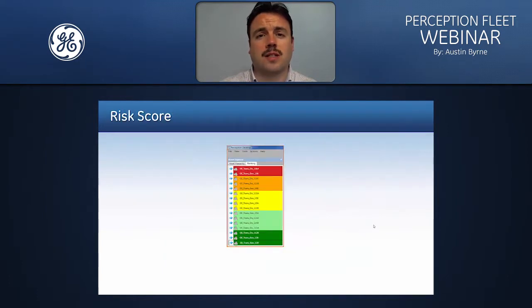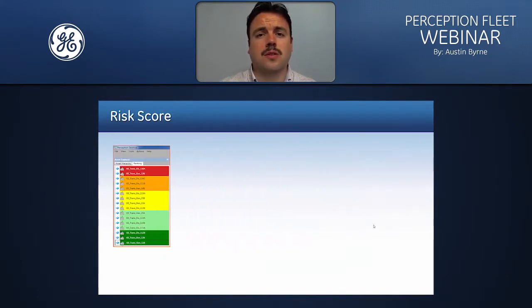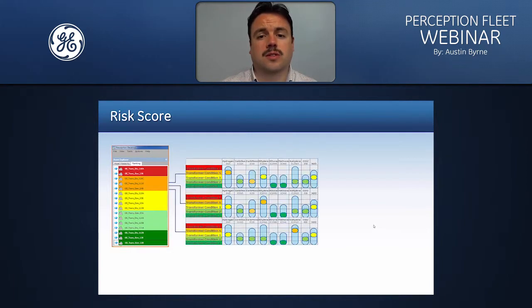Something else that we apply to the asset is a risk score. And the risk score allows us to categorize the asset within the fleet tree. So you can see, for example, we have 2 assets in this table that are in category 5, which is indicated by the red. But which of those assets is in the worst condition? If you have multiple assets all falling within the same risk index, how do you know which one is the most important and the one that needs to be looked at first? And that's why we calculate the risk score.